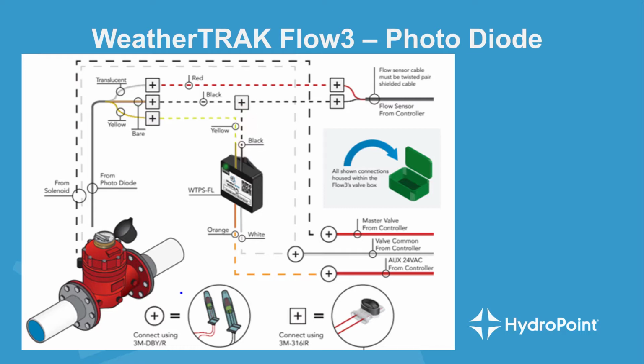Begin by finding the black wire in the picture of the power supply. You'll notice that it connects both to the bare copper coming from the flow sensor and to the black wire on your flow sensor pair, or the FL negative, coming from the controller.